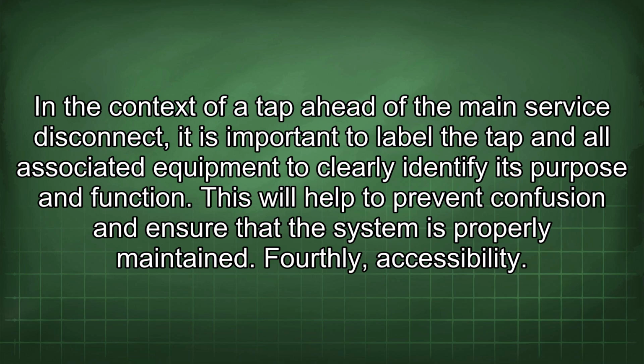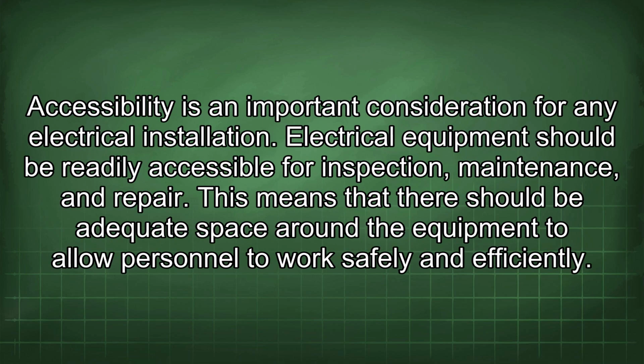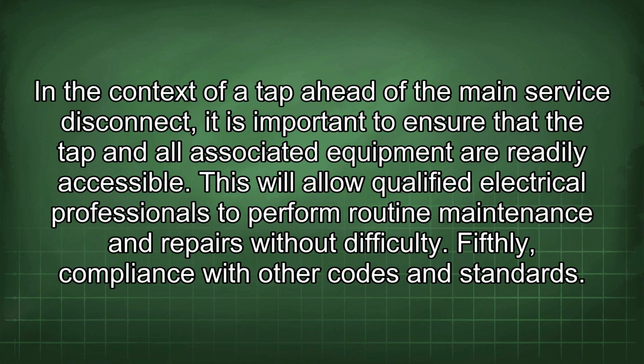Fourthly, accessibility. Accessibility is an important consideration for any electrical installation. Electrical equipment should be readily accessible for inspection, maintenance, and repair. This means that there should be adequate space around the equipment to allow personnel to work safely and efficiently. In the context of a tap ahead of the main service disconnect, it is important to ensure that the tap and all associated equipment are readily accessible. This will allow qualified electrical professionals to perform routine maintenance and repairs without difficulty.